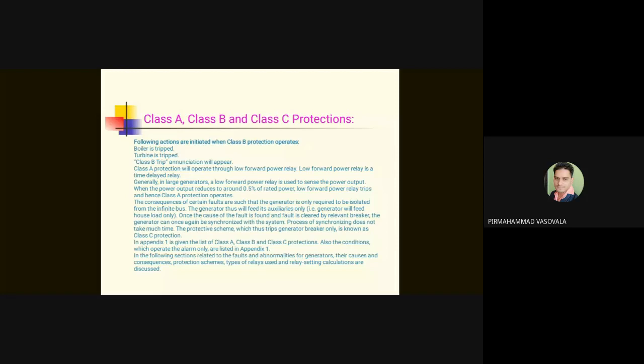In class C, we only trip the breaker. We don't trip anything else. We keep the turbine running. We keep the boiler running. We keep all auxiliaries running. The generator will run on its house load, that is 10% of the rated power that is required for the generator itself. The generator will keep on running on the house load, and connecting the generator back to the bus takes hardly 5 minutes or less, because it needs only synchronizing the generator to the bus. Therefore, a lot of time which otherwise is lost in class A or class B protection is saved in class C.